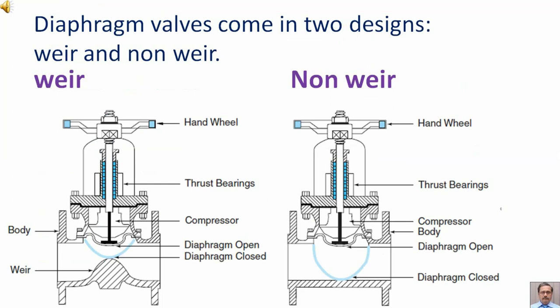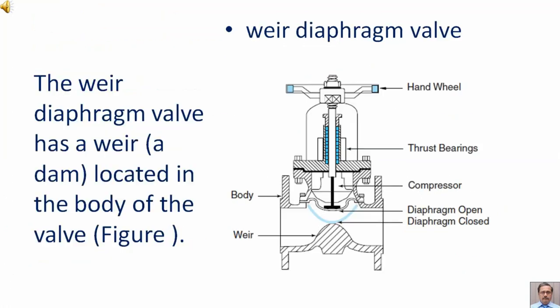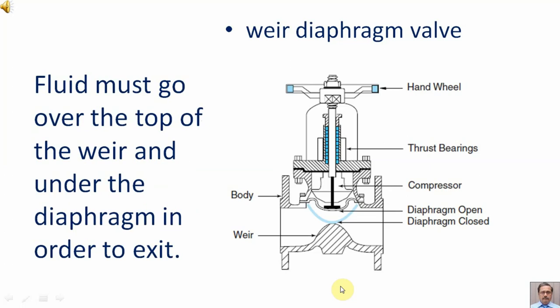Diaphragm valves come in two designs: weir and non-weir. The weir diaphragm valve has a dam located in the body of the valve. Fluid must go over the top of the weir and under the diaphragm in order to exit.